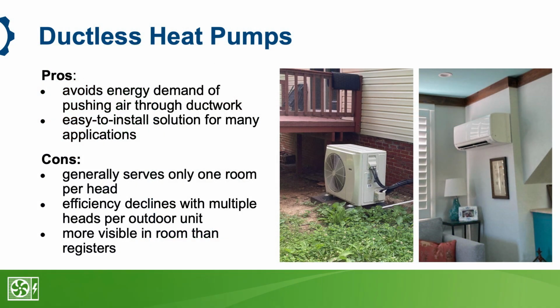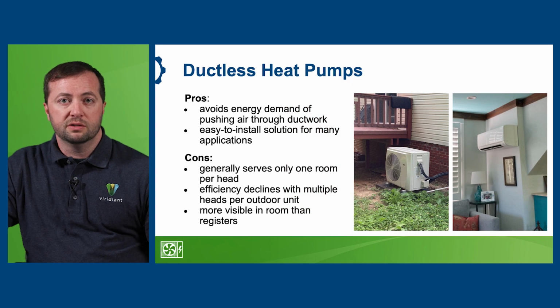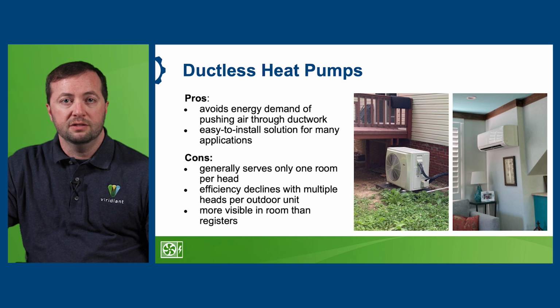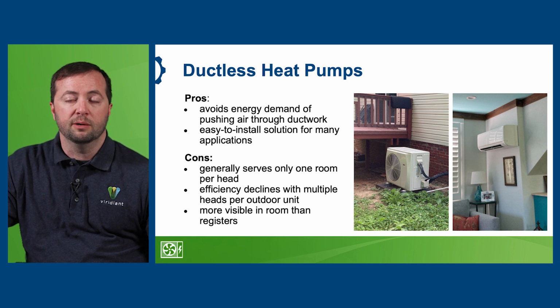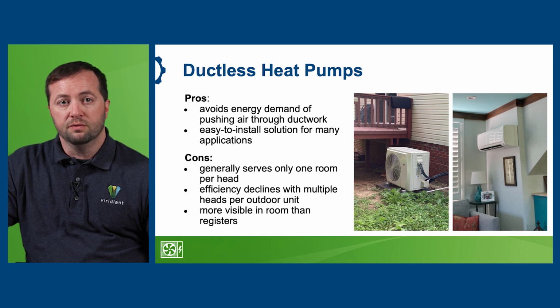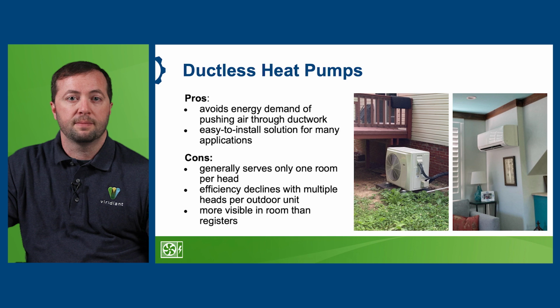Now let's look at ductless mini splits, what most people think of when they hear the term mini split. For homes and buildings without existing ductwork, these provide a great way to switch to a heat pump for a lower cost. They come in a very high SEER, that's the Seasonal Energy Efficiency Ratio, and HSPF, the Heating Seasonal Performance Factor, which is the less often referenced winter heating spec. Just remember that just because it's ductless doesn't mean it's super high performance. There are ductless models with mediocre specs too. But all ductless models avoid using additional fan energy to push air through a duct system and thereby avoid losing heating and cooling to the outside via duct leakage.